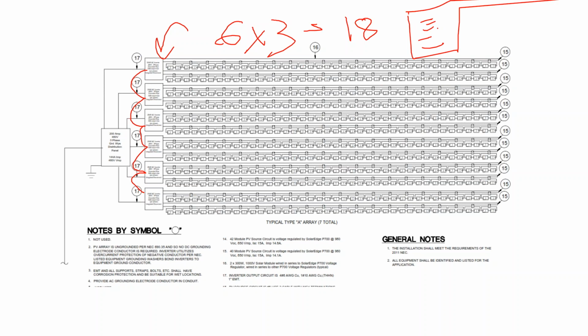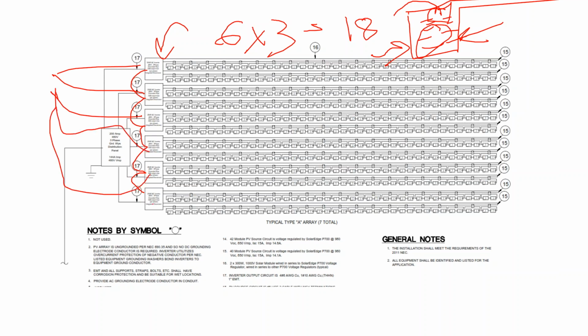And so the question is, well, if you have all these empty spots, is it better to use the empty spots or not? And the difference is if you fill up all those empty spots on your utility scale design, you may have to specify a panel board that also has a main breaker switch. And so we've kept our string inverters to 6 so that we don't need to have a main breaker on this panel. We can just turn each inverter off at the panel using these breakers.